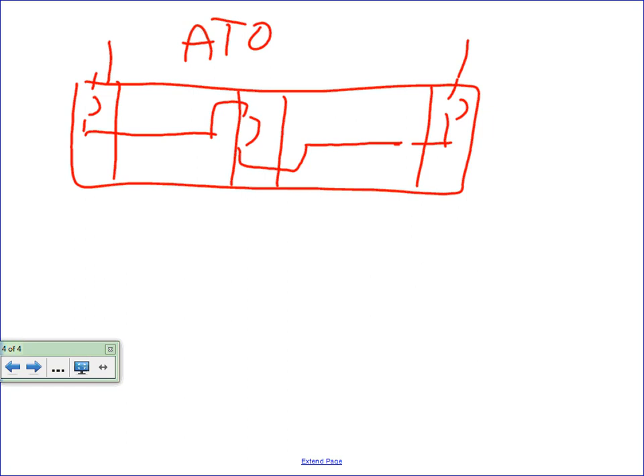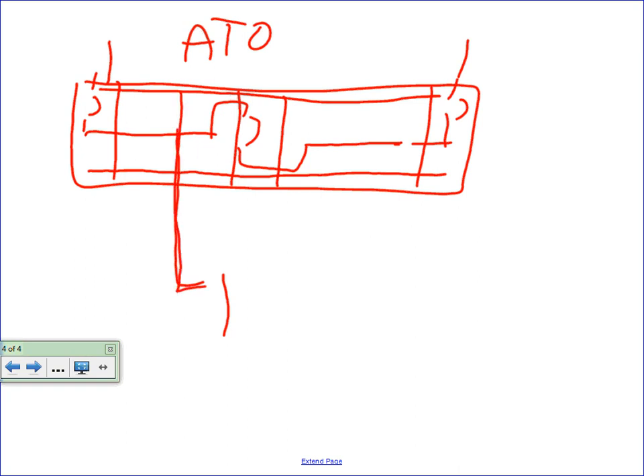Because whenever you have a system like this, you still have your ground and your neutral bus tied together. The tie isn't necessarily switching that with the 3-pole breaker. So now, all of a sudden, you have a ground fault. Well, what happens is now the power, instead of coming back on the neutral to the switchboard from that source, is going to ground.